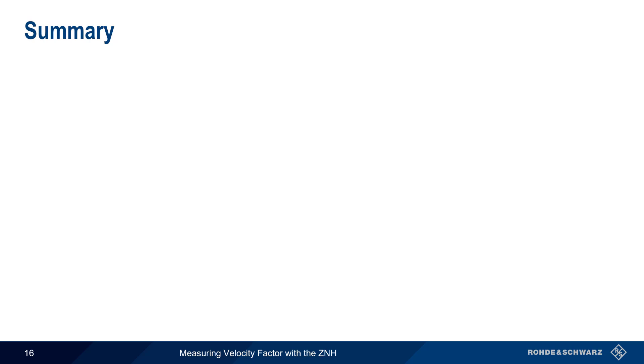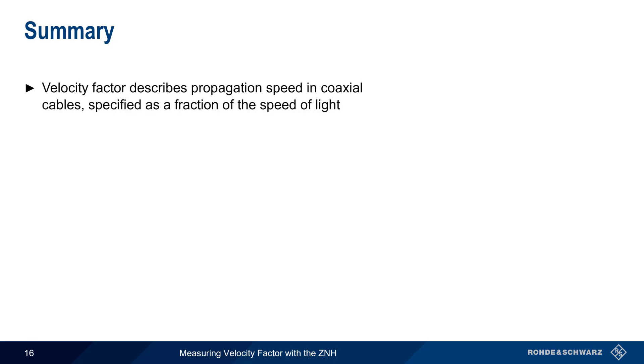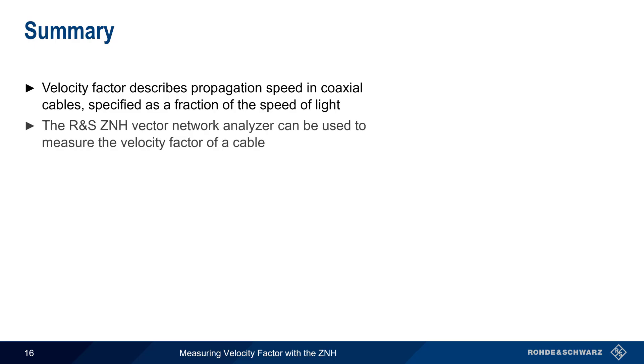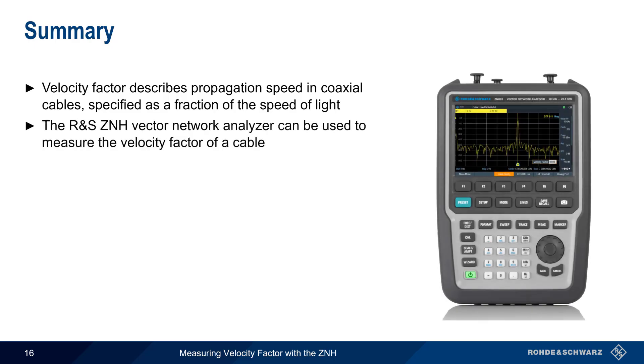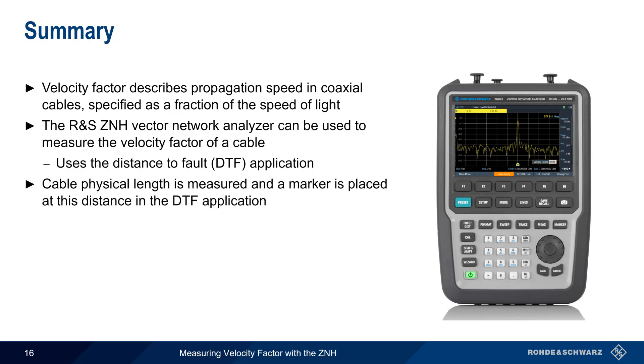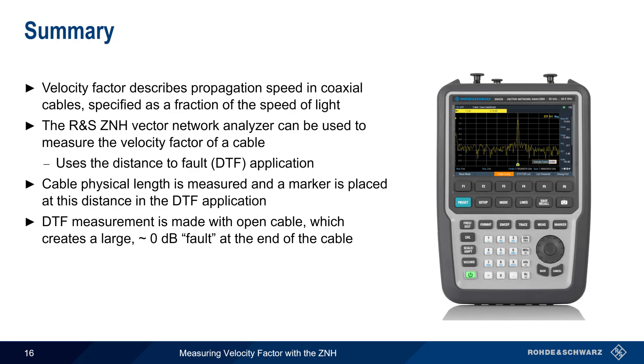Let's end with a brief summary. Velocity factor describes the propagation speed of signals within a coaxial cable and is specified as the fraction of the speed of light in a vacuum. The Rohde & Schwarz ZNH vector network analyzer can be used to measure velocity factor using its distance-to-fault functionality. The cable's physical length is first measured and a marker is placed at this distance in the DTF application. When the DTF measurement is run on an open or un-terminated cable, this will cause a large, near 0 dB fault at the open end of the cable. Velocity factor can then be determined by varying the user-defined velocity factor until this end-of-cable fault coincides with the marker placed at the known length of the cable.